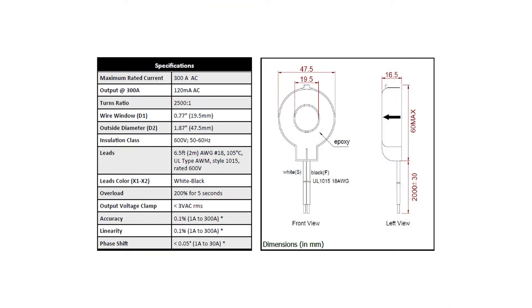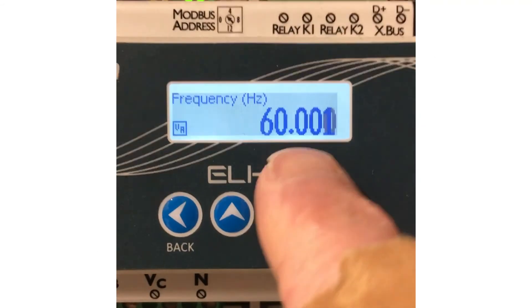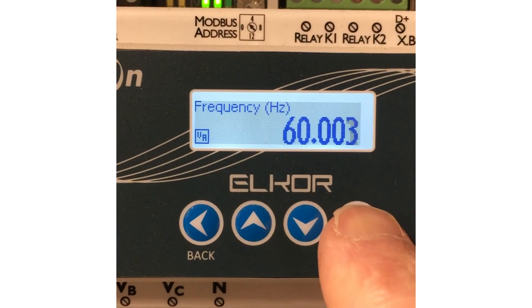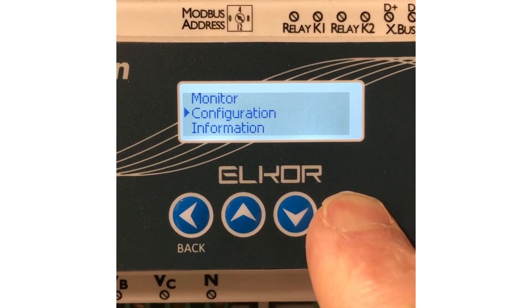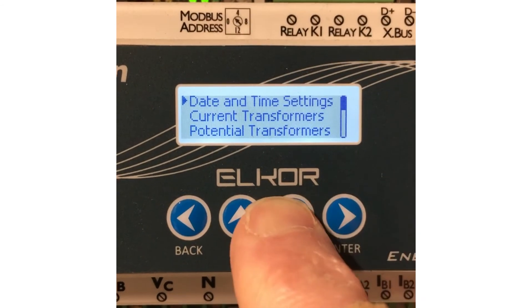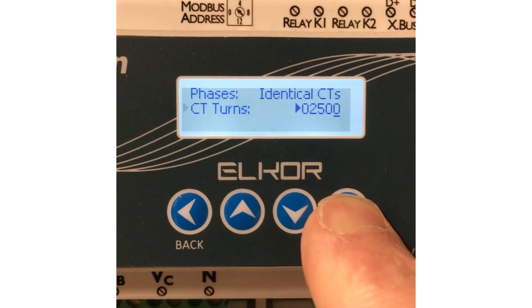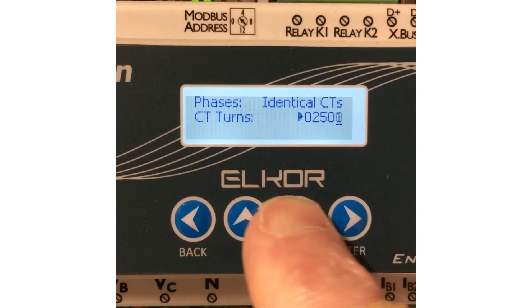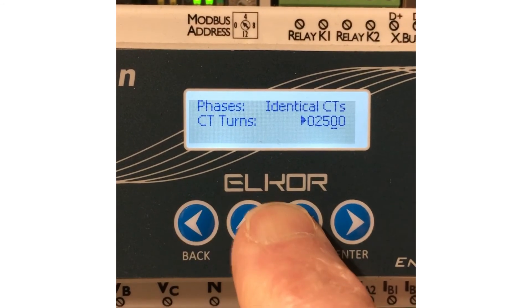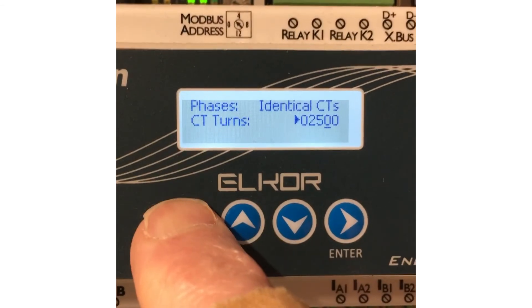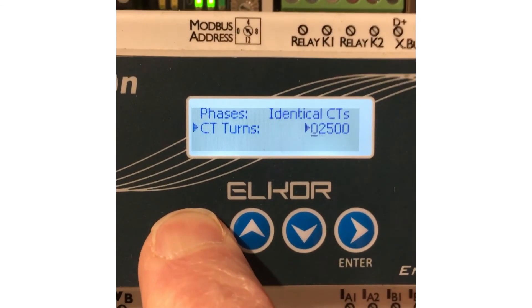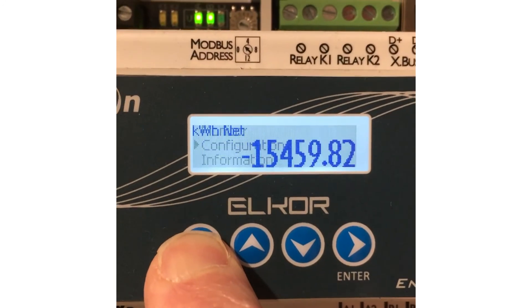The turns ratio for the CTs being used must be set. For the MCTA CTs used in this video, the turns ratio is 2500 to 1 for both. On the front of the Elkor meter, press the right arrow, use the down arrow to select configuration, and then the right arrow to enter the configuration menu. Press the down arrow and then the right arrow to open the current transformer menu. For identical CTs, press the down arrow then the right arrow to set the turns ratio. The digit with the line beneath it can be changed by pressing the up or down arrow. Move to the left by pressing the left arrow. When done, press the left arrow until CT turns is selected, then three more times to return to the home screen.